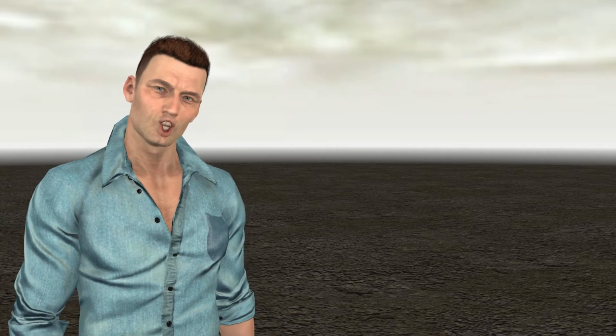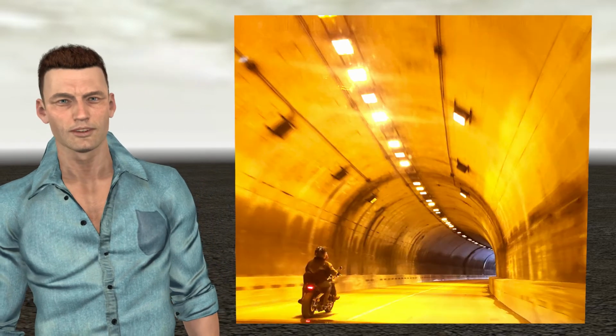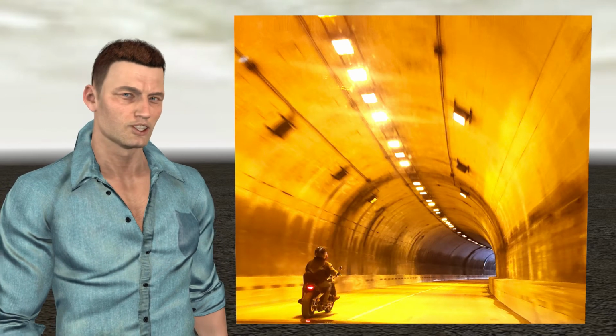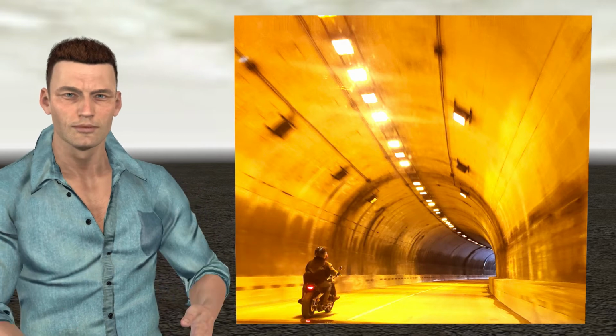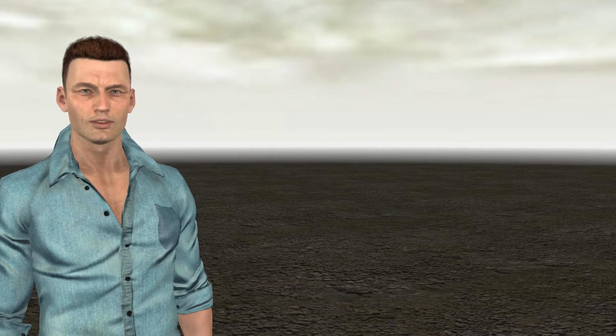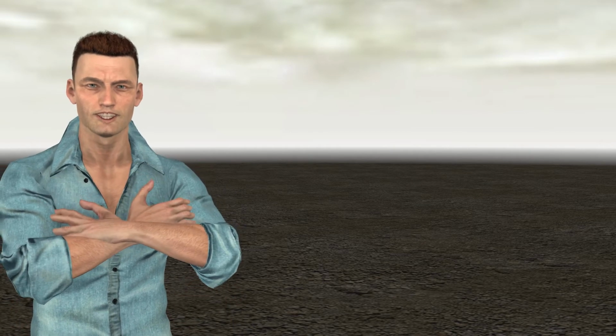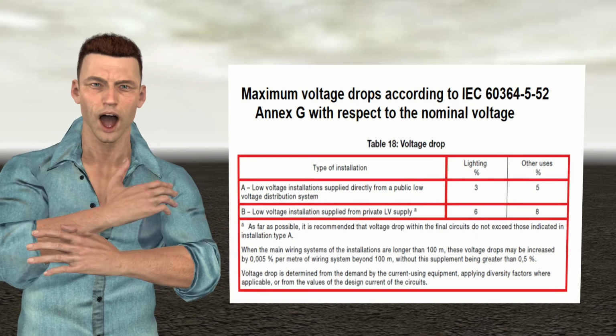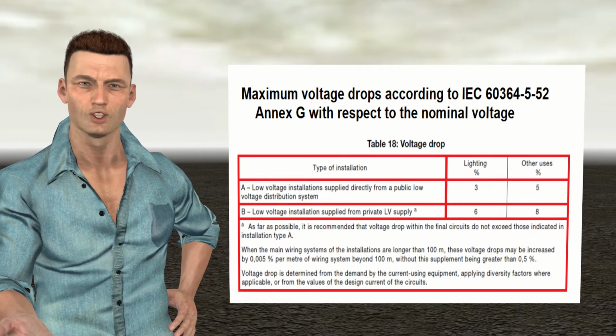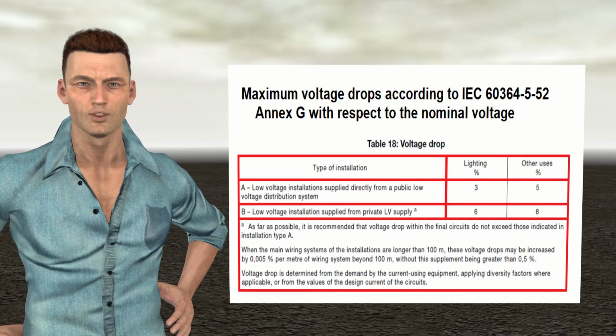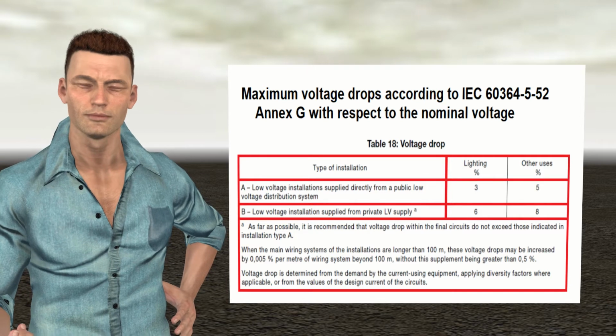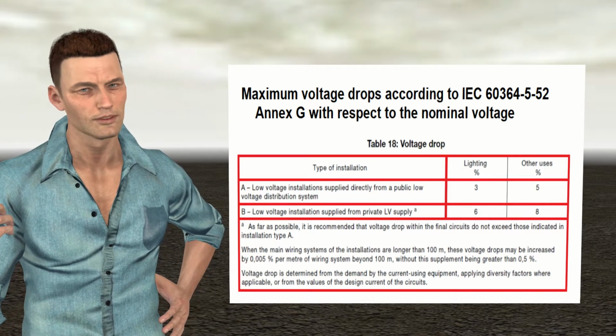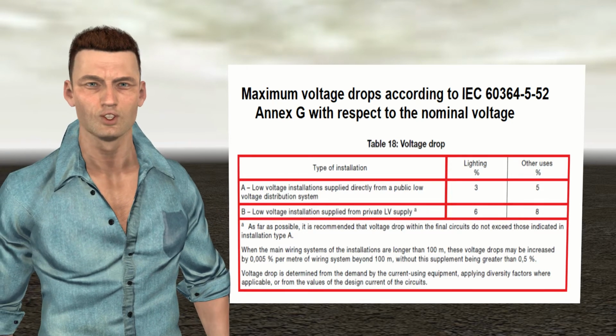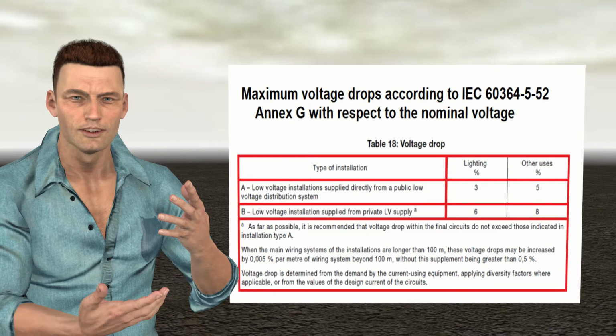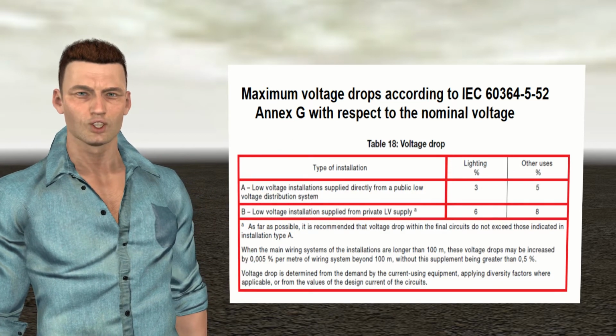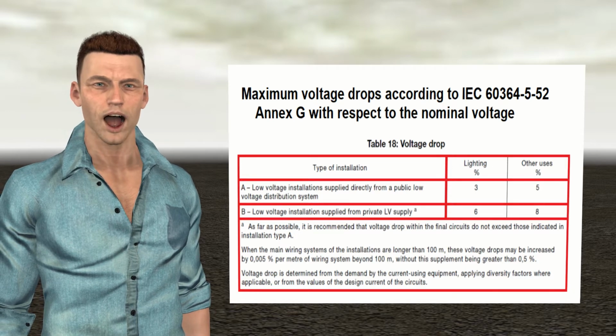Perhaps in an indoor installation such as that of our houses, this aspect is not so critical, but if, for example, we consider a long tunnel, an excessive voltage drop could affect the lighting of the furthest luminaires from the transformation center. Standards in each country establish maximum voltage drops. For example, the standard IEC 60364-5-52, in Annex G, states that the voltage drop between the origin of an installation and the load connection points should not be greater than the values indicated in the following table, expressed with respect to the nominal voltage of the installation. In this way, if we consider a low voltage line, with a nominal voltage of 230 volts, and a maximum voltage drop of 3%, the difference in voltage between the two ends of the line should not be greater than 6.9 volts.